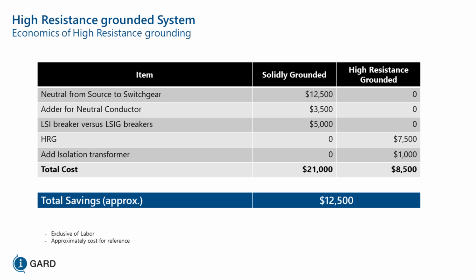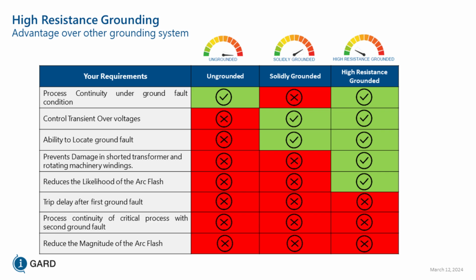system of $12,500. So it's less for a high resistance grounded system than a solidly grounded system. Now, one thing you are sacrificing is you don't have the use of the 277 volt load. But you could put in isolation transformers where you're servicing 277 volt loads and end up with a safer system.